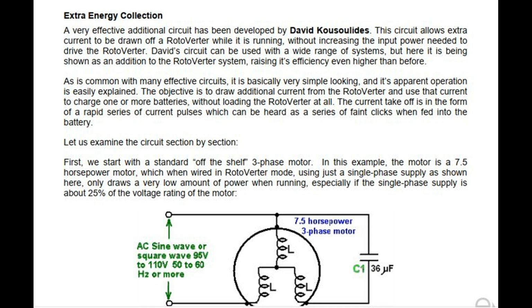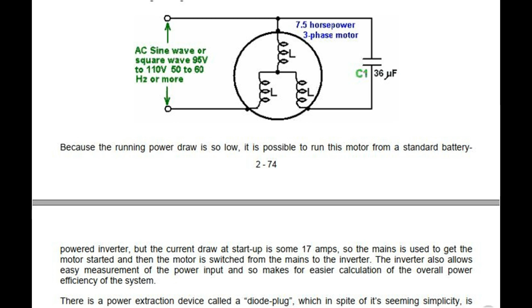First, we start with a standard off-the-shelf three-phase motor. In this example, the motor is a 7.5 horsepower motor, which when wired in rotoverter mode, using just a single-phase supply as shown here, only draws a very low amount of power when running, especially if the single-phase supply is about 25% of the voltage rating of the motor. Because the running power draw is so low, it is possible to run this motor from a standard battery-powered inverter, but the current draw at startup is some 17 amps, so the mains is used to get the motor started and then the motor is switched from the mains to the inverter.